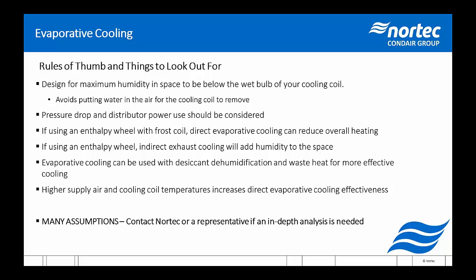If you're using an enthalpy wheel, a full energy wheel, and that energy wheel has a frost coil on it, so that's a preheat coil for the enthalpy wheel, the direct evaporative cooling can actually reduce the amount of overall heating. So there's two different ways of using an enthalpy wheel to avoid frosting. You can either reduce the amount of airflow over it by slowing down the wheel or bypass dampers, or you can preheat the outside air. And if we're preheating the outside air, obviously we're getting less cooling effect from that outdoor air. And when we add in the evaporative cooler, we can reduce the amount of heat we need to apply. If you're using an enthalpy wheel, again, the indirect exhaust cooling will add humidity back to the space. So that's just something to keep an eye out for.